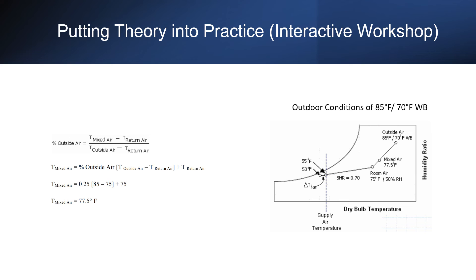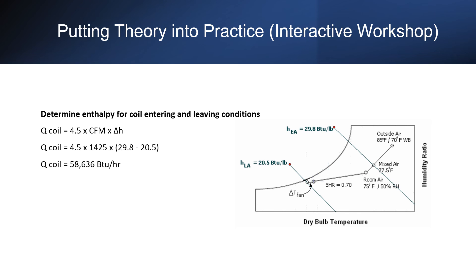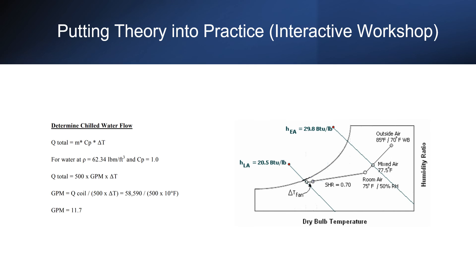Locate the mixed air condition and account for fan delta T. Assuming perfect mixing occurs, the mixed air conditions can be found using this equation. On the psychrometric chart, plot the enthalpy for coil entering and leaving conditions, and from the following formula, calculate the coil cooling load. The last step is to calculate the chilled water flow through the coil. Since we know the cooling requirement and delta T across the coil, we can simply use the following formula to calculate the required flow.